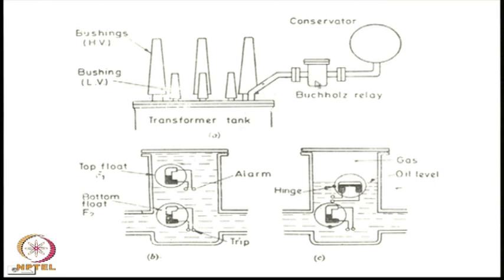This usually consists of a chamber which is normally filled with oil, and it consists of 2 trip floats which hold 2 contactors. In the normal situation, this chamber will be filled with oil, and both the float contacts will be open. However, if there is some short circuit, some fault, so that there is overcurrent in the transformer, gases will be generated because of heating of the transformer oil, and since this is filled with oil, the gas will move up and will push the oil level down. As a result, since this is hinged, the top float will turn around and will possibly close a contact here, which will sound an alarm and tell the operator that something is wrong.